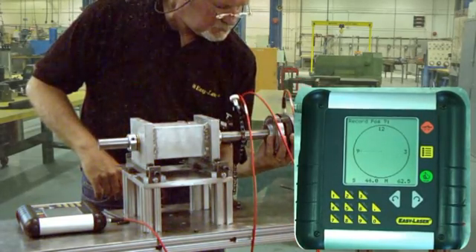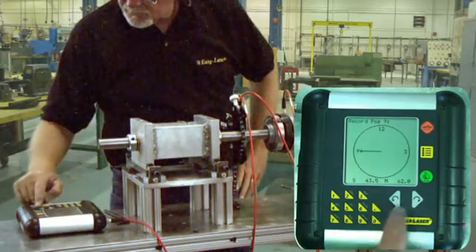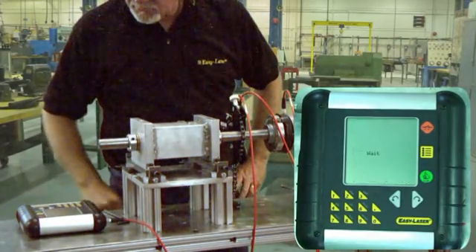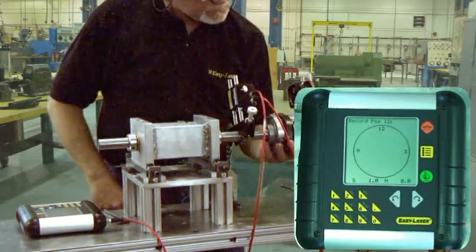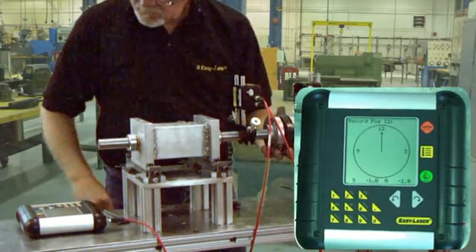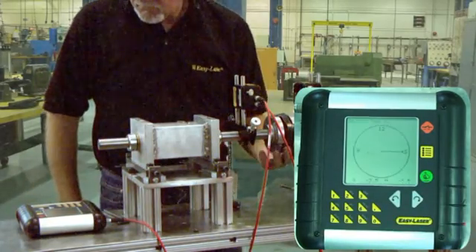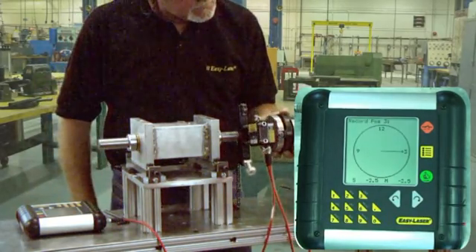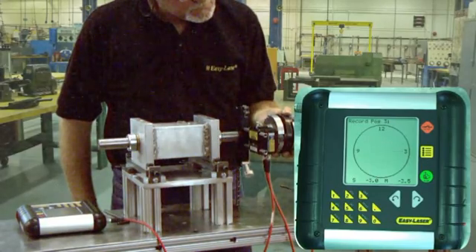The screen prompts us to move the measuring units to the 9 o'clock position and record the measurement. We do the same for 12 o'clock and 3 o'clock. We do not rush this. We want a good stable reading. Remember it's easier to hit a fixed target than a moving one.